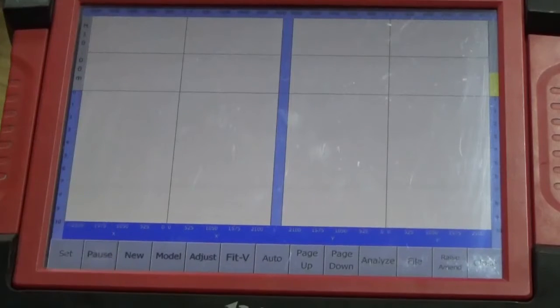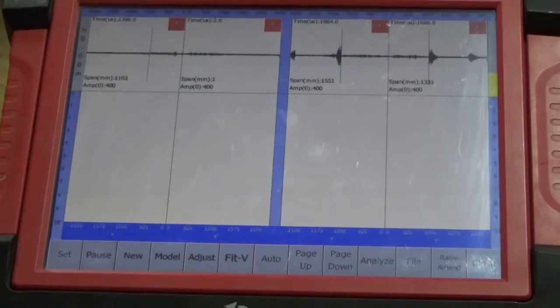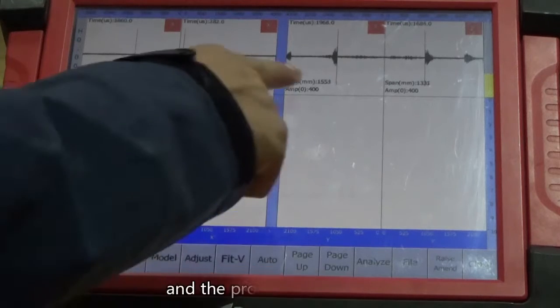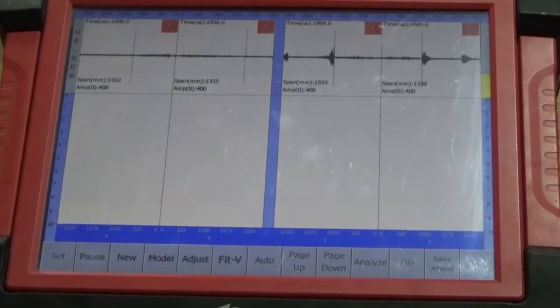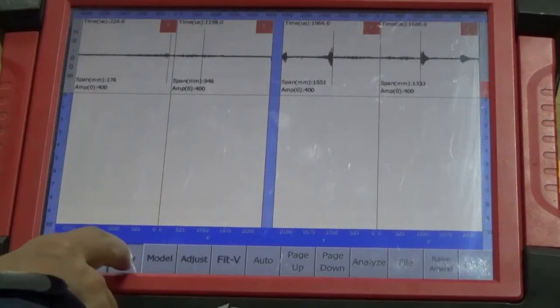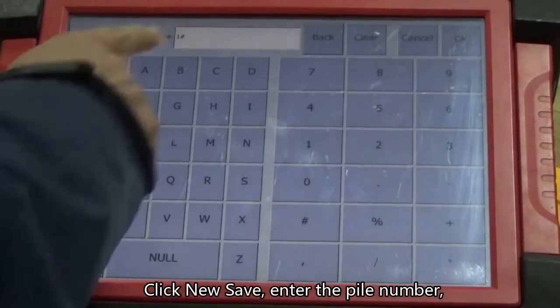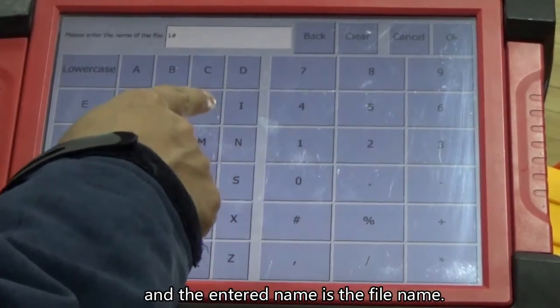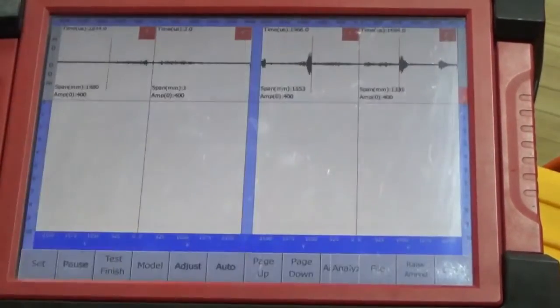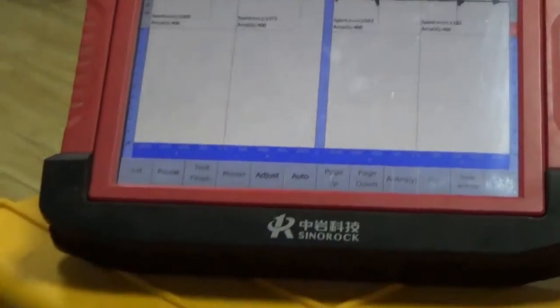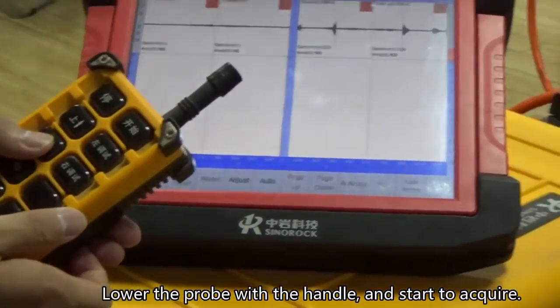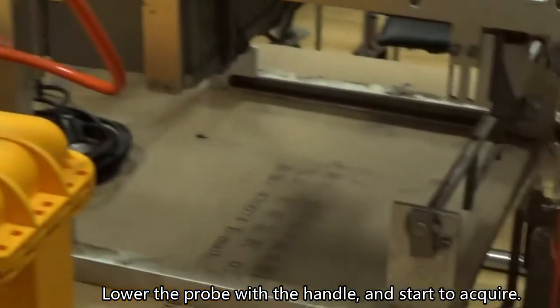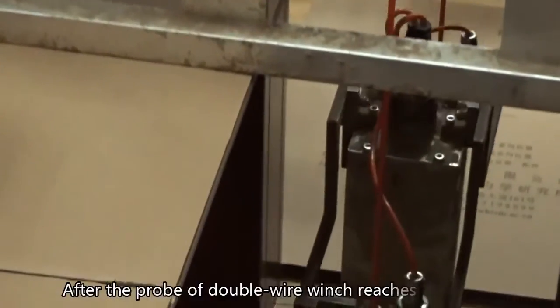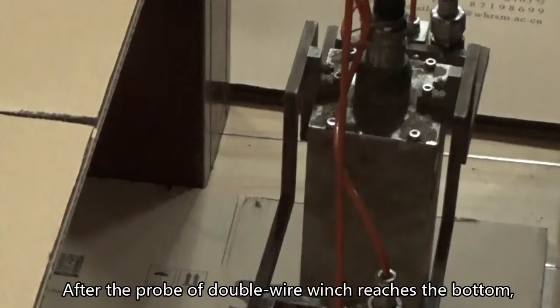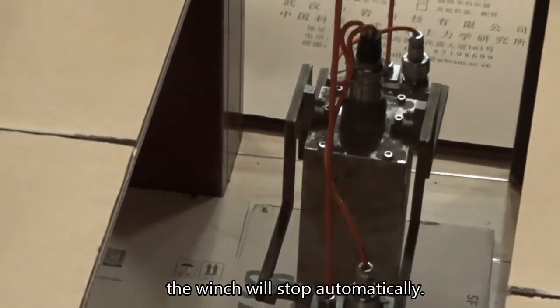Click Sample. And the probe will start to work. Click New Save, enter the pile number. And the entered name is the file name. Lower the probe with the handle. And start to acquire. After the probe of double wire winch reaches the bottom, winch will stop automatically.